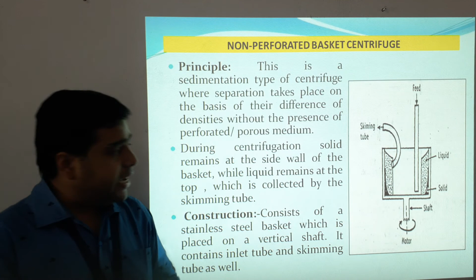Construction consists of a stainless steel basket which is placed on a vertical shaft. It contains inlet tubes and skimming tubes as well. This is the inlet tube and this is the skimming tube. Come to its working. The suspension is fed continuously into the basket. During centrifugation, the solid phase is retained on the sides of the wall and the liquid remains at the top. So after the process, the solids are retained on the side walls and the liquid phase comes to the top.